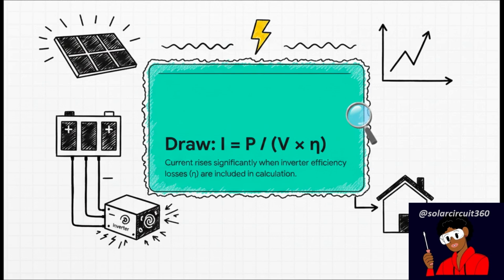But the complete real-world equation for DC current draw estimation is this: I, the current, equals P, the power, divided by V, the voltage, multiplied by eta, which is the inverter's efficiency factor. Because your system's voltage is fixed at a nominal 48 volts, the only way to deliver 5 kilowatts of power is by yanking a massive amount of current from those batteries.